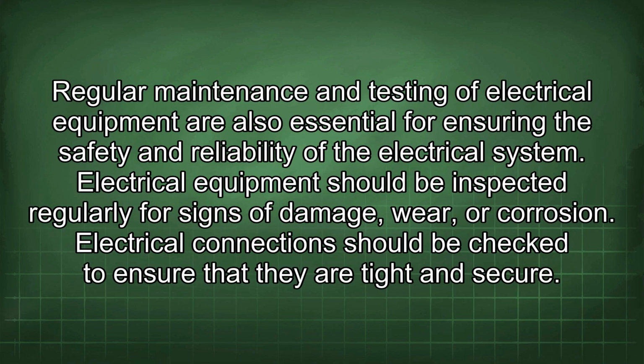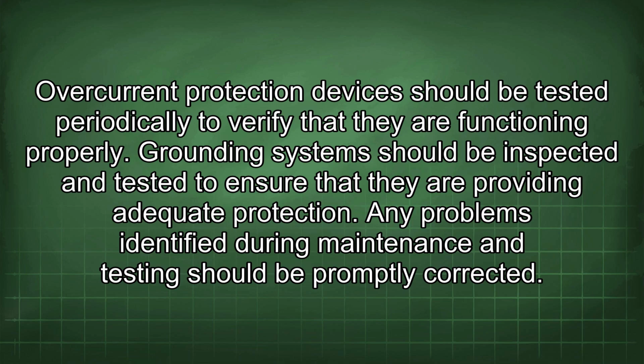Regular maintenance and testing of electrical equipment are also essential for ensuring the safety and reliability of the electrical system. Electrical equipment should be inspected regularly for signs of damage, wear, or corrosion. Electrical connections should be checked to ensure that they are tight and secure. Overcurrent protection devices should be tested periodically to verify that they are functioning properly. Grounding systems should be inspected and tested to ensure that they are providing adequate protection. Any problems identified during maintenance and testing should be promptly corrected.